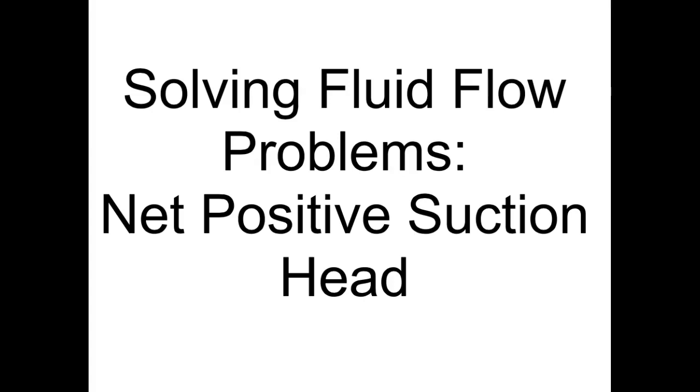Net positive suction head means that you have suction coming in on the suction side. So you have lower pressure on the suction side than you have on the discharge side. But your pressure doesn't drop so low that you start cavitating, which can wreck your pump. So you need a certain amount of suction head, or the ability to actually pull your fluid through the process to the pump for your pump to work properly. So let's take a look at how this works.